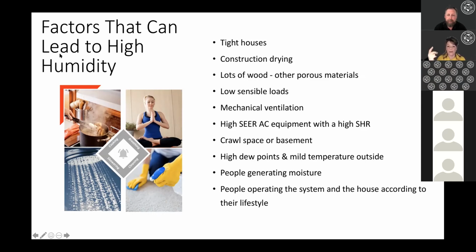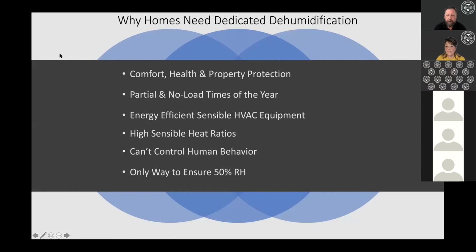So we've got to think about other ways to control moisture, because moisture is the number one detriment to our homes. We need dedicated dehumidification, typically in the Carolinas, for comfort, health, and property protection. A lot of times in shoulder seasons - spring, fall, overnight - we're not running much air conditioning, and the tighter our houses get, the goal is to run even less. We've got energy efficient equipment, but we can't control human behavior, and dehumidification is the only way to ensure 50% relative humidity.